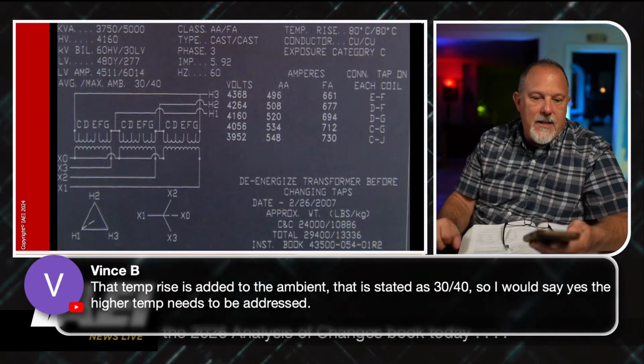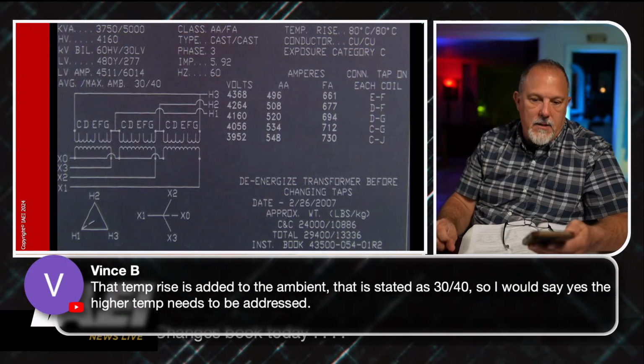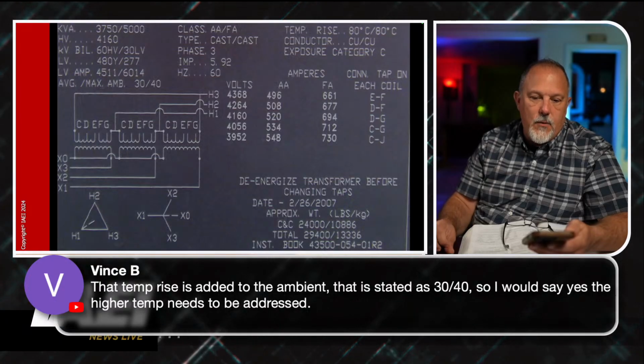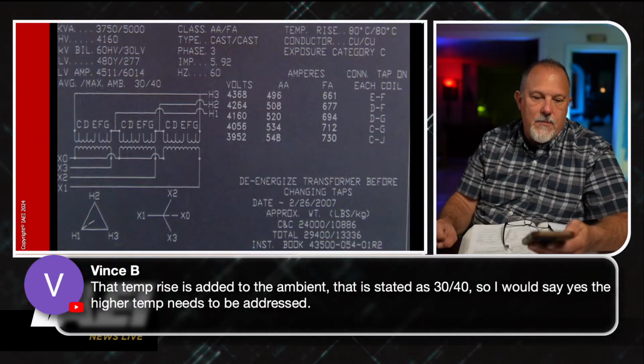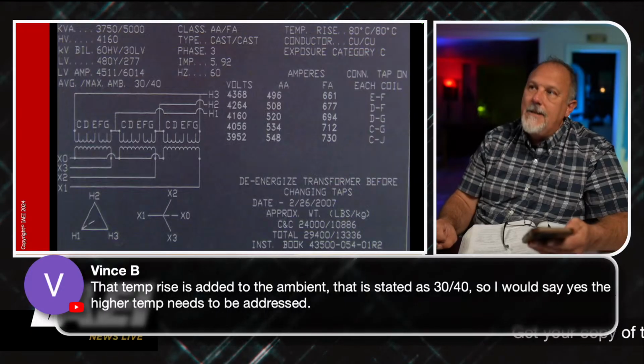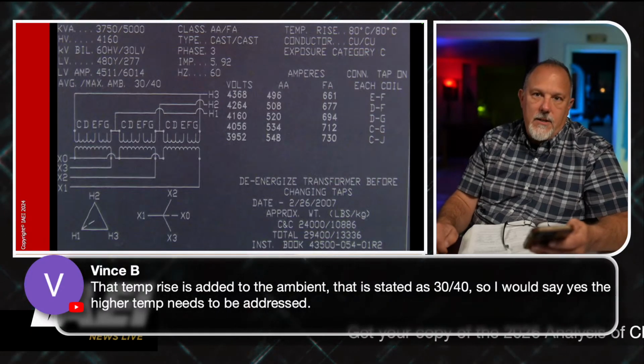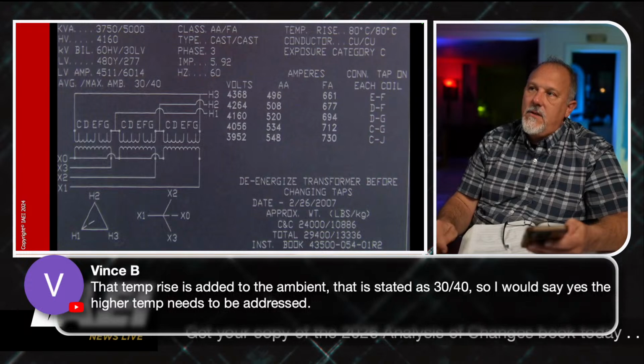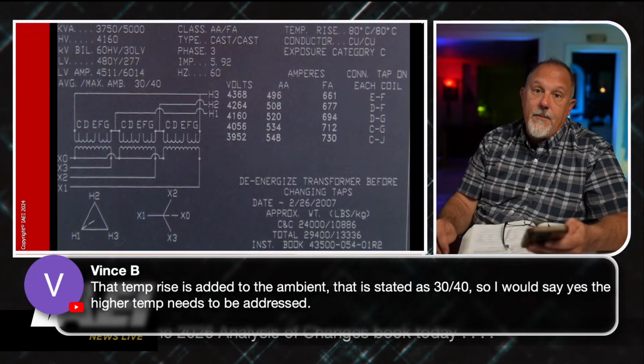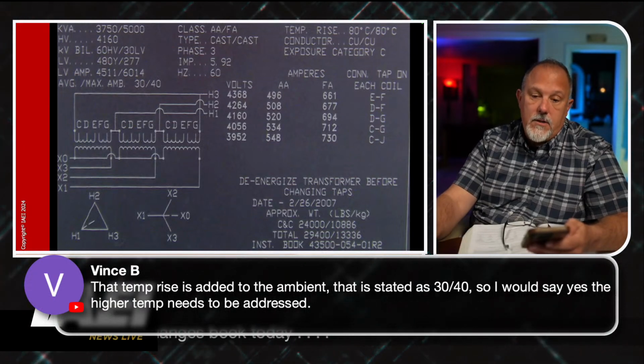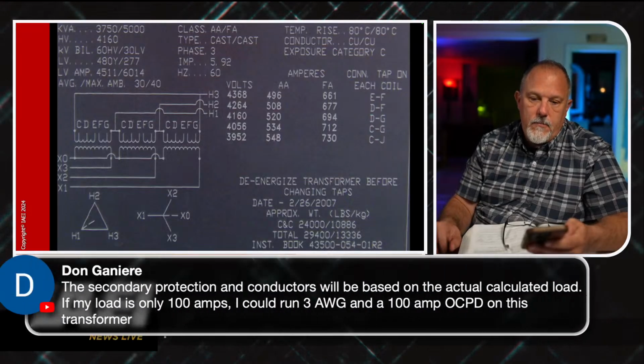Vince B, that temperature rise is added to the ambient. That is stated as 30 to 40, so I would say yes, the higher temperature needs to be addressed. Vince, you're probably right. I definitely have to do more homework on that. I'm going to go with your lead, Vince. You sound a lot smarter than I do.